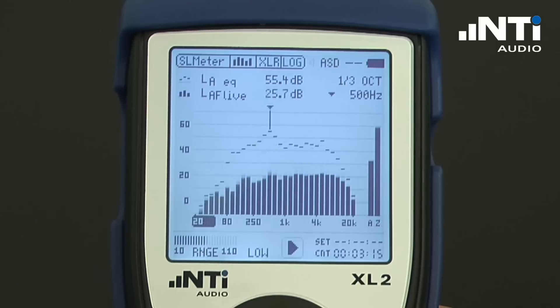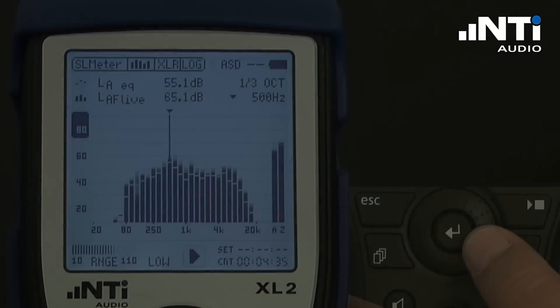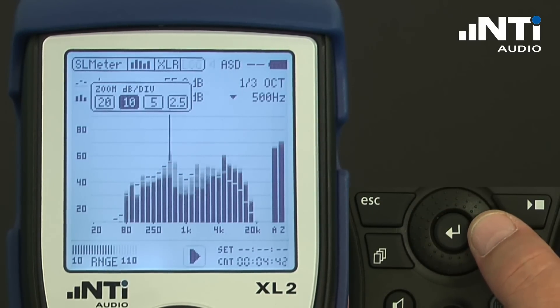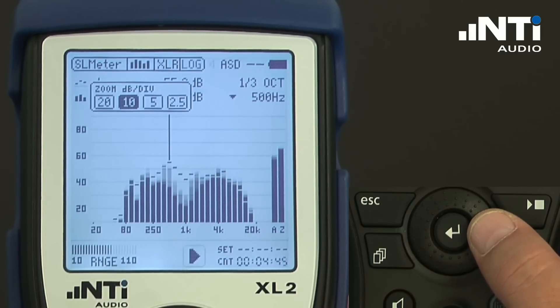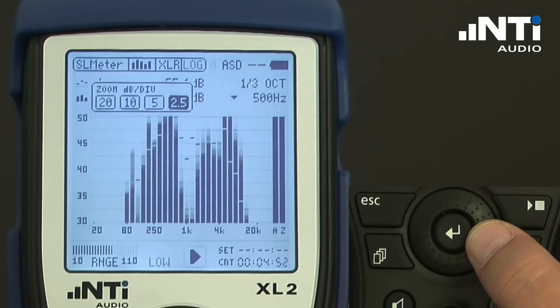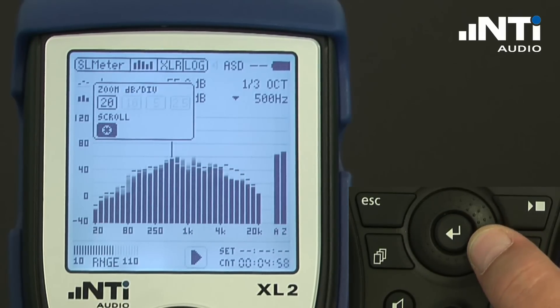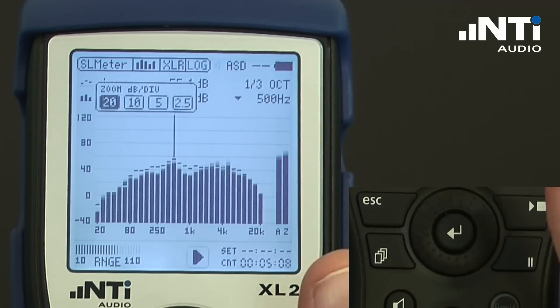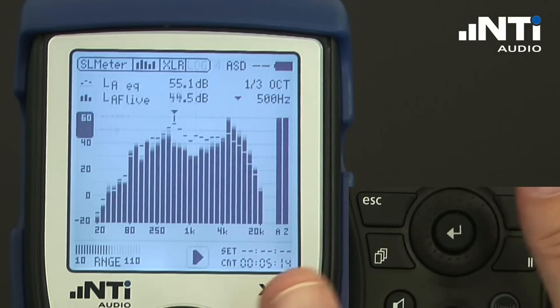The Y scale can be altered by placing the cursor to the maximum of the Y scale. After pressing enter, we can select the sensitivity in dB per division — it can be 20 dB, 10, 5, and 2.5 — a very sensitive range. After this, we have the scroll that allows us to move the scale up and down until it fits our requirements. If I want to change back to 10 dB, I press again, go to 10, and move the scale up and down until it fits my expectations.